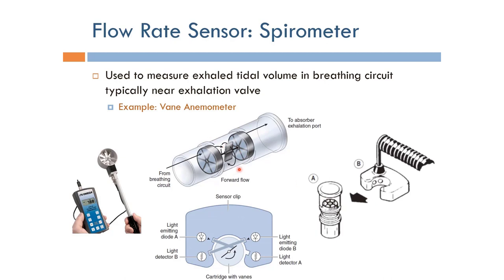We have optical paths going through this piece. Whenever this is in position, the path between this LED and this light detector is cut off. So we keep getting pulses on and off between these two sensors, and based on those pulses we can compute the number of rotations.